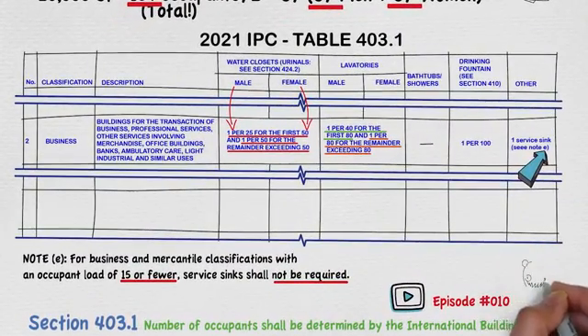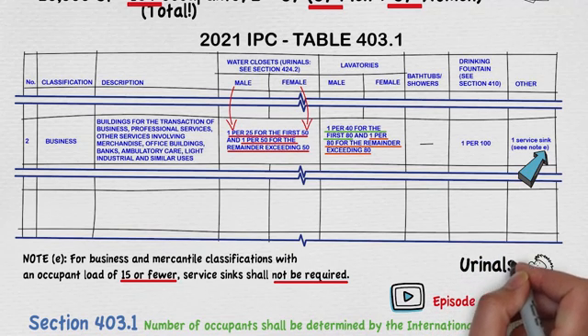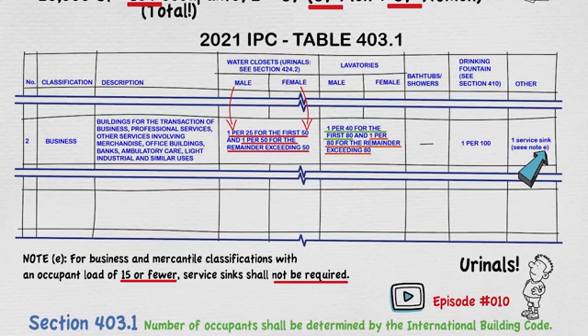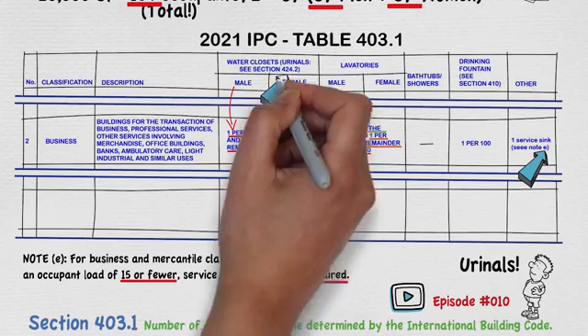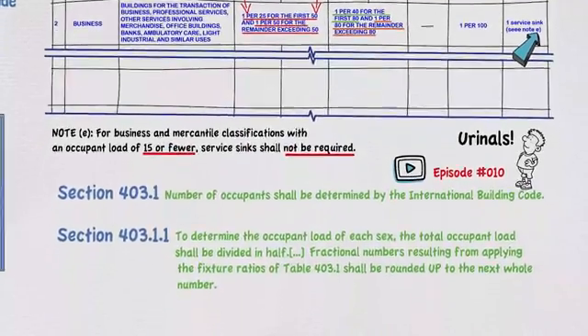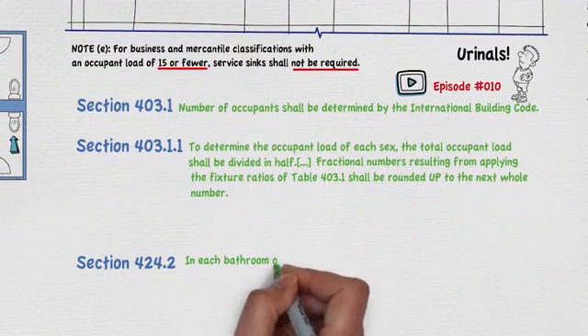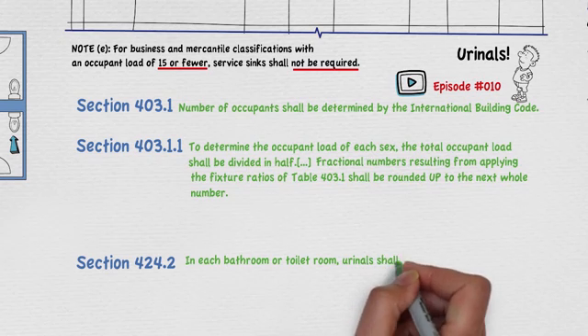Now we're almost done, but if you look at the chart there are no other fixtures to calculate — so what is missing? If you said we are missing urinals, you are correct. The International Plumbing Code does not have a separate section for urinals. The chart has a note in the water closet section referring to section 424.2, which states: urinals shall not be substituted for more than 67% of the required water closets in assembly and educational occupancies, and not more than 50% in all other occupancies. Since our occupancy is not assembly or educational, we can substitute up to 50% of the water closets for urinals. Since we need 3 water closets, we can substitute 1 water closet for a urinal.